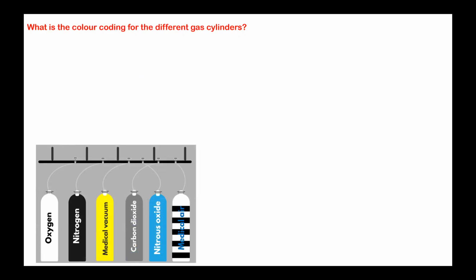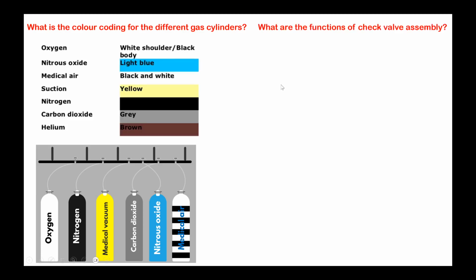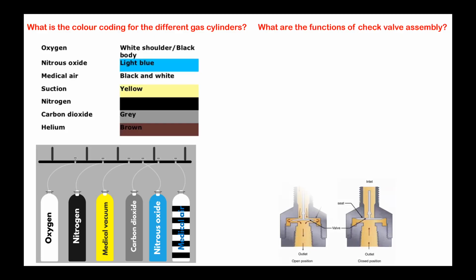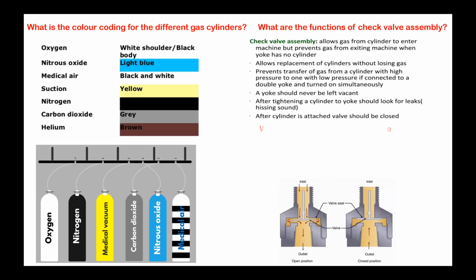In the color coding, why is there color coding? What is the purpose of doing this color coding for different gas cylinders? To avoid wrong filling and misconnections. First of all, for easy identification. By seeing the color, you can say, oh, this is nitrous oxide because it is blue. Oh, this is carbon dioxide because it's gray. And the second thing, even people who are illiterate can easily identify the black cylinder or white cylinder. And the second reason is you will not be fixing it to the wrong yoke assembly. And the check valve assembly is another safety device in the yoke.